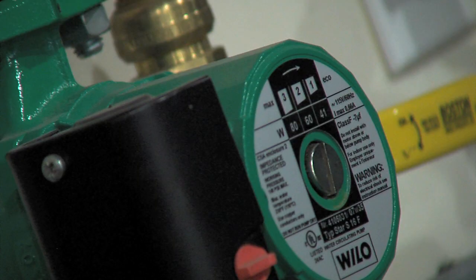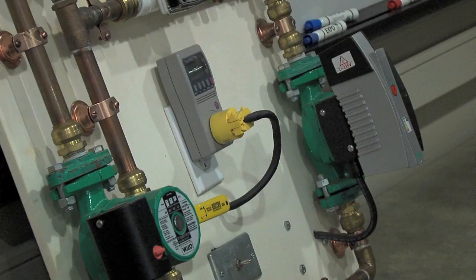Do you retrofit old pumps with those controls? Absolutely. Some of the things that you'd actually retrofit the pump. It'd be a pump replacement. You change the pump? Yeah, because you have to have that permanent magnet on the shaft in order to do it. You can retrofit these with a drive, but when you think about the cost of that versus its payback, it's difficult.